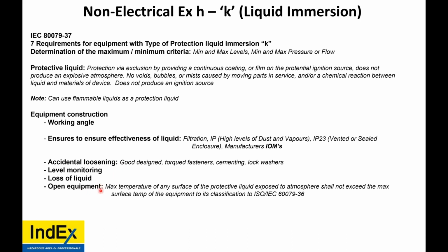And opening of equipment, if there's any parts that can be opened, the maximum temperature of any surface of the protective liquid exposed to atmosphere shall not exceed the max temperature of the overall piece of equipment. So if the equipment is rated T3, 200 degrees, if you open one piece of it, which is meant for inspection or filling it with more oil or liquid, that one area shall not be greater than the temperature of 200 degrees, like the overall device is rated for.